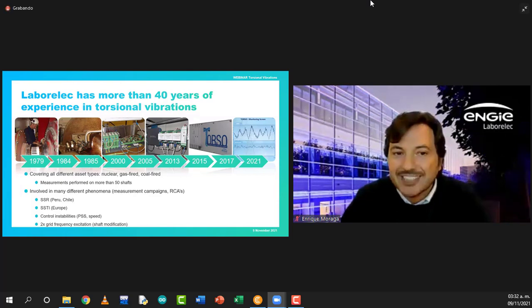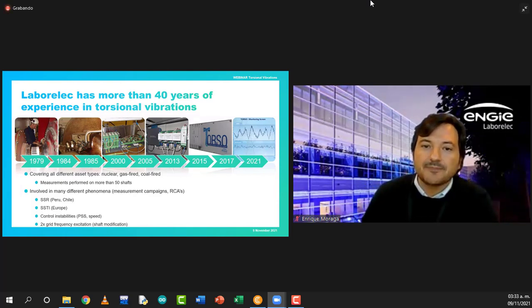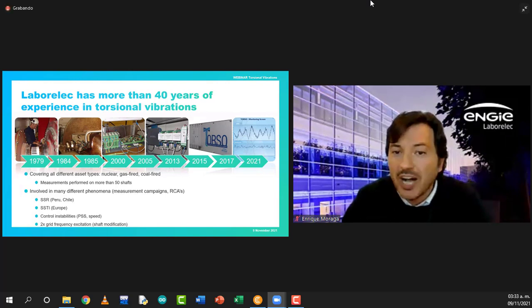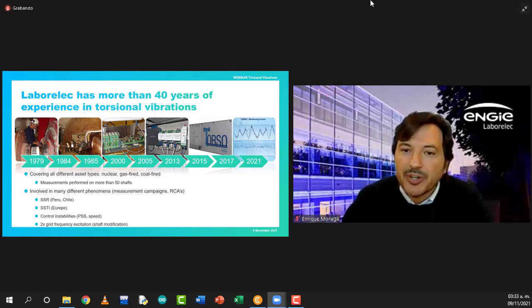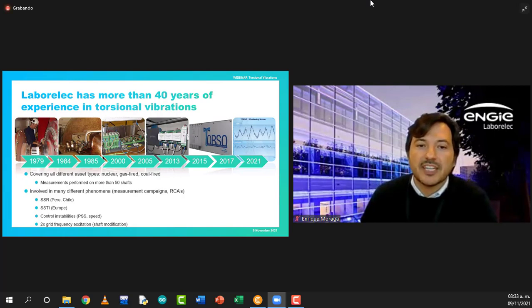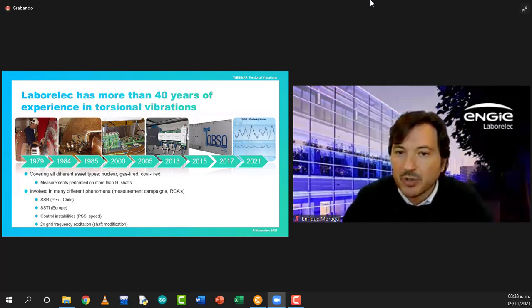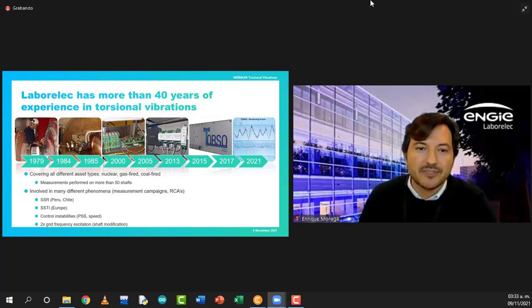And in 2016, a catastrophic failure occurred in Latin America on a gas turbine with only 200 operating hours. After this major issue, as Fritz commented before, the subject became quickly a hot topic all over Latin America, to the extent that the grid operator obliged every power plant to perform a costly risk assessment or to install a torsional vibration monitoring and protection system. So at that time, Laborelec upgraded the device, implementing the protection feature, and the first Torso Protect was installed in 2017. Until now, more than 50 installations have been carried out worldwide, covering all different asset types.